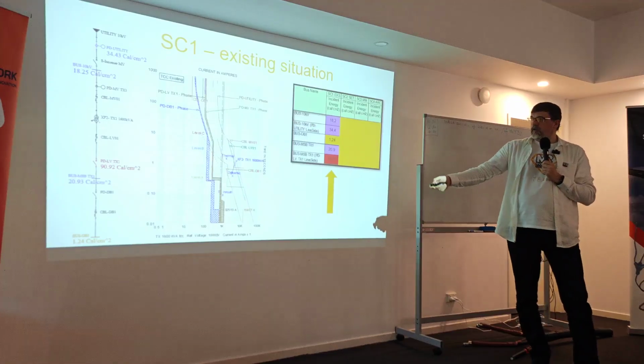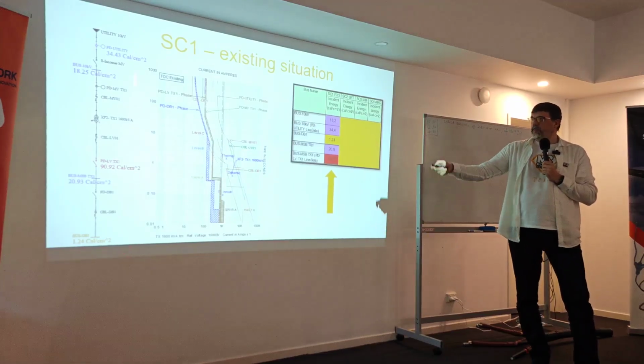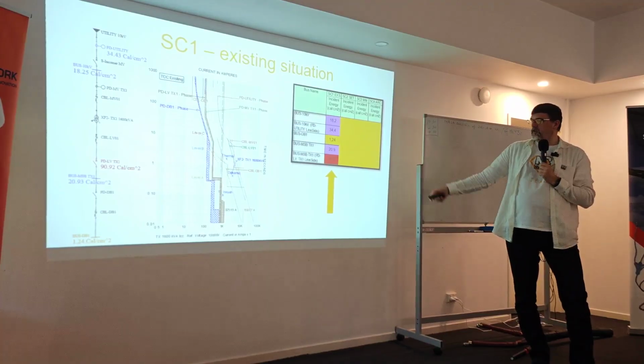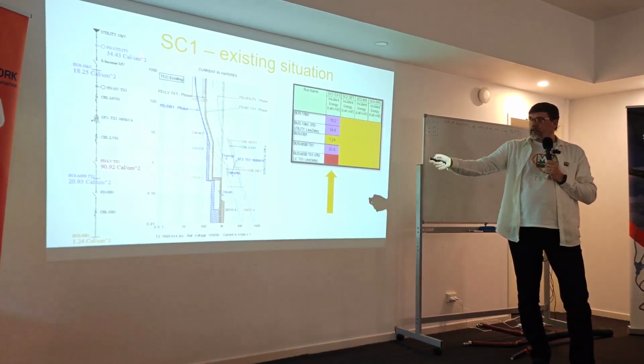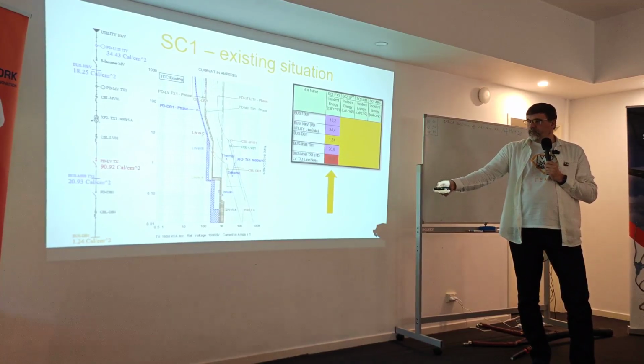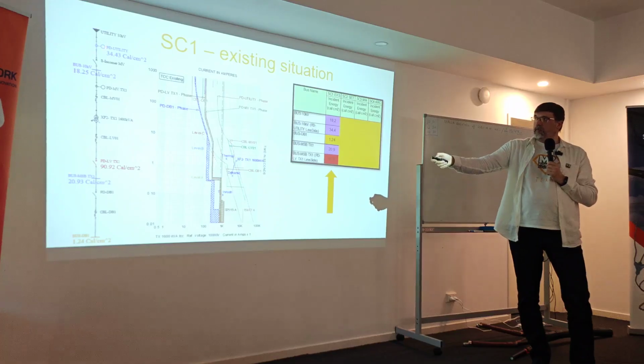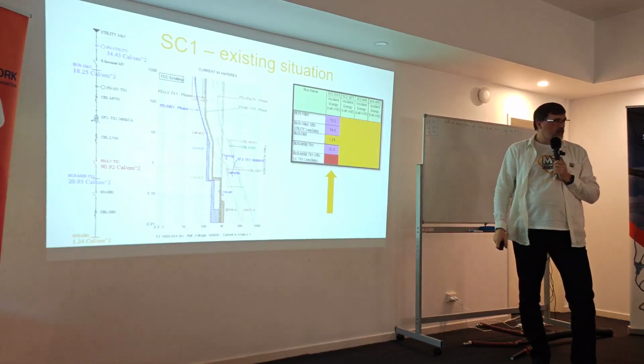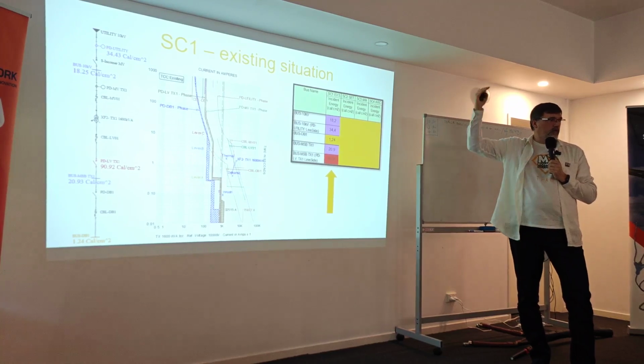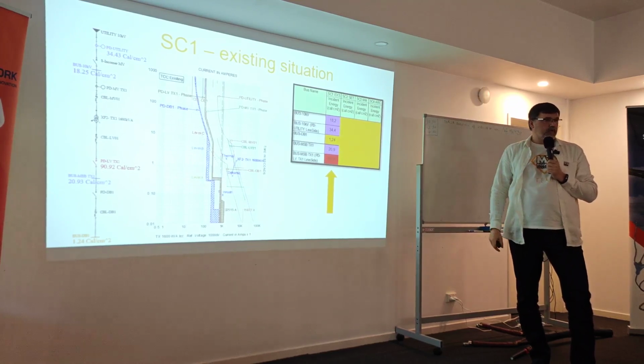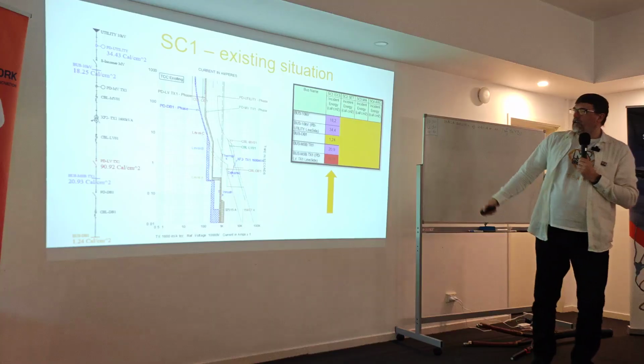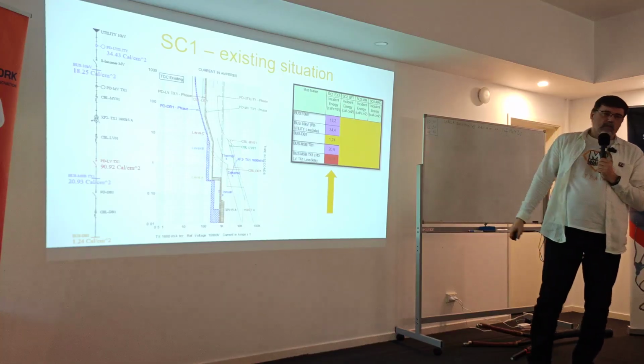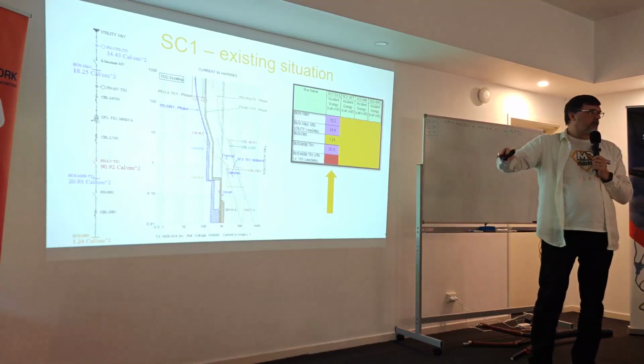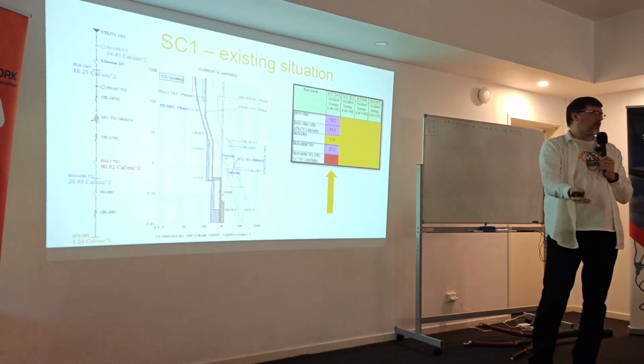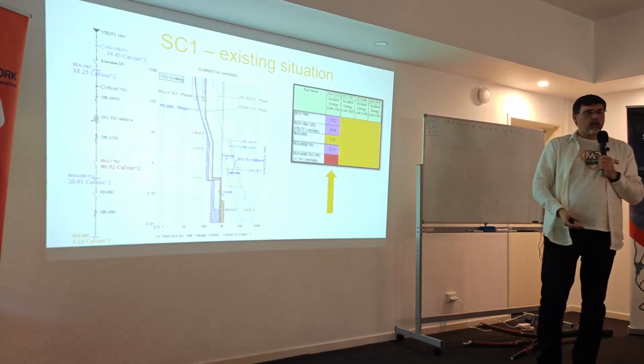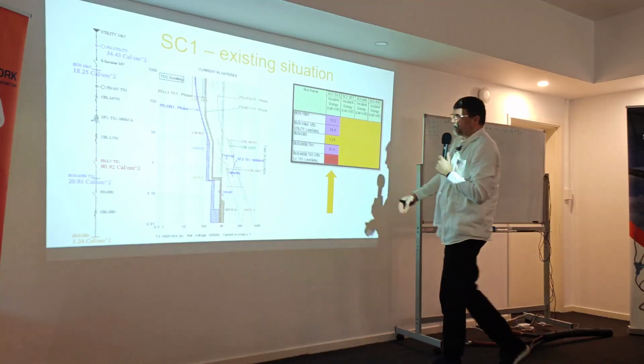So when we go with this, and this is part of a very simplified calculation, I will try to show you the concept. On the left, you see the single line. We look mainly at this because on the main incomer, on the medium voltage, nothing will change, because I don't show you the upstream things. So there's a starting point. And then we have this thing in the middle, a TCC, time current curves. So protection, a graphical representation of the overcurrent protection settings. Yeah. And technically this is okay.